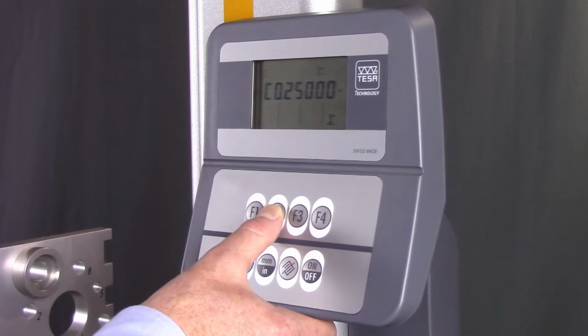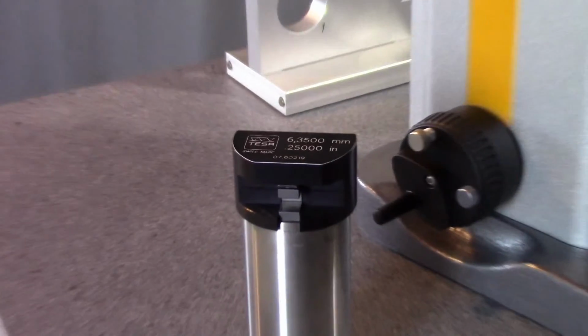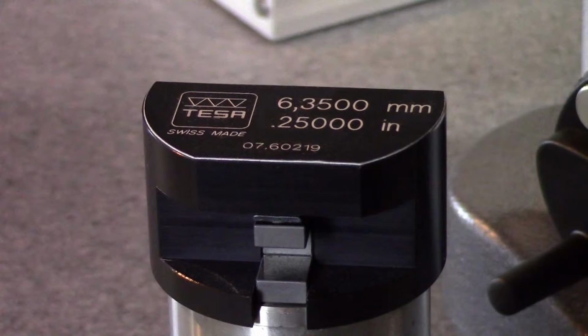Calibration requires just a few steps and puts the gauge into Start 2 mode, which allows you to measure in two directions. Start by pressing F2 and establishing the probe constant using the setting master. It's important that the setting master diameter matches the displayed value that appears on the screen when you press F2. In this case, the display reads 0.25000 and the setting master is also 0.25000.